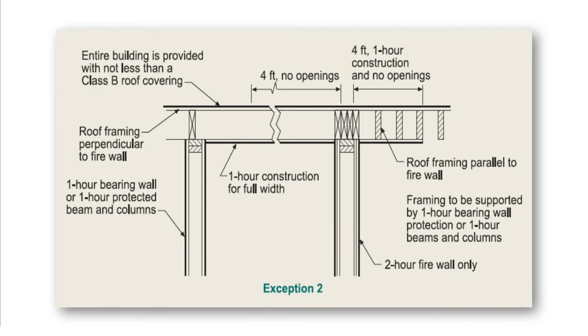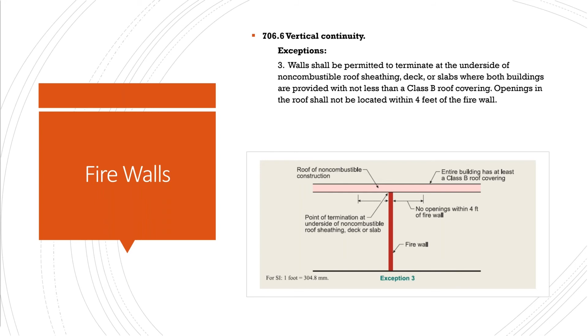And then exception 3 with its visual is when, instead of extending 30 inches up, walls shall be permitted to terminate at the underside of non-combustible. Make sure you're reading these clearly, which exception goes with what: stepped roofs, 2-hour walls. This one's for non-combustible roof sheathing, deck, or slabs, where both buildings are provided with not less than a Class B roof covering. Openings in the roof shall not be located within 4 feet of the firewall. That was an easy one.